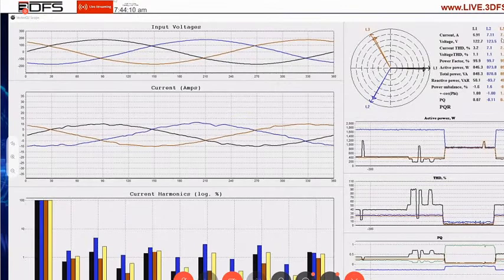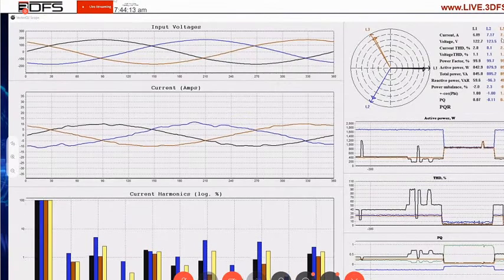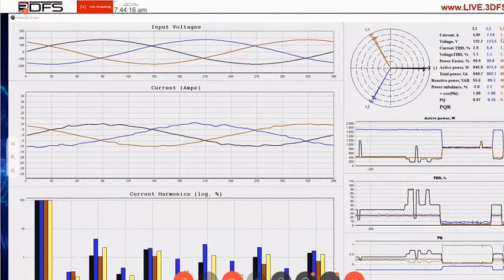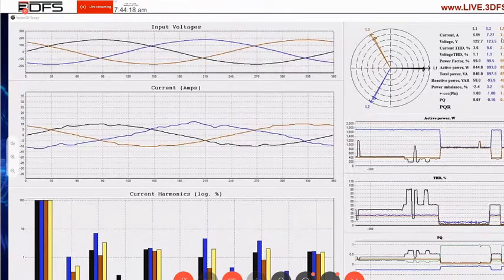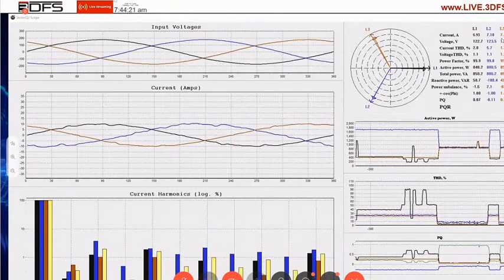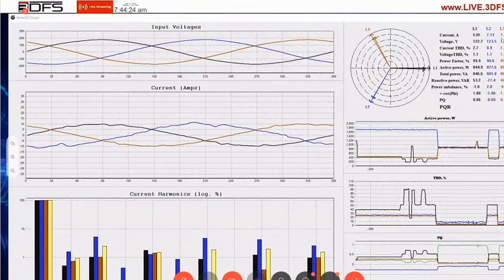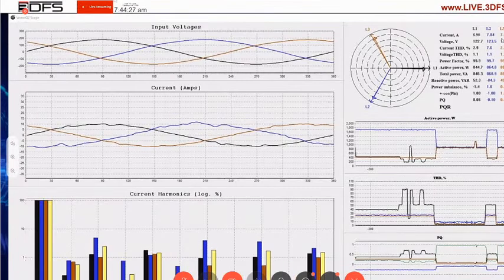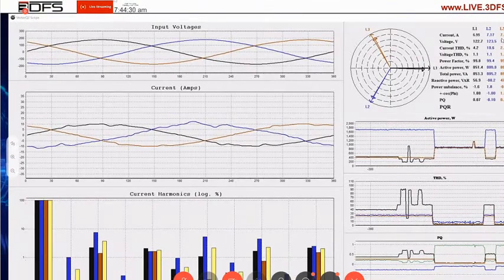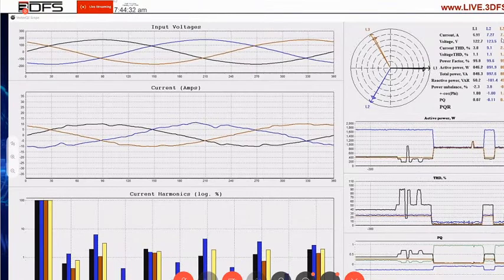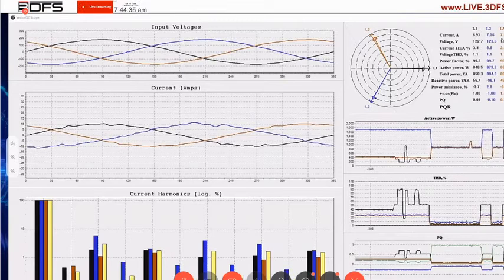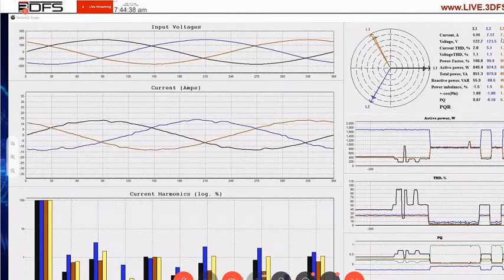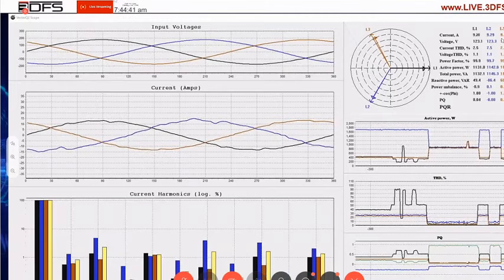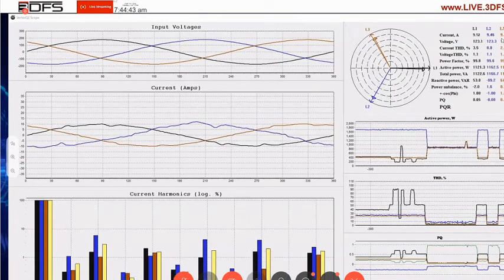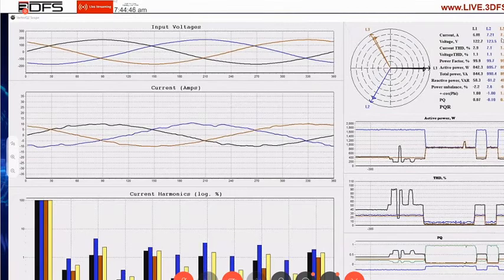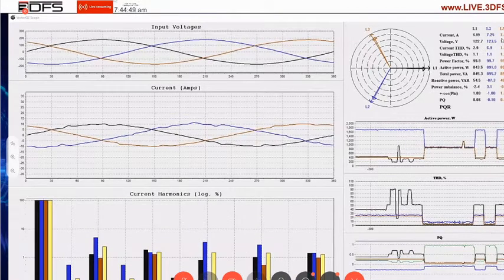Now the way we're doing that is within the device there's a DC bus bar. We are pulling the power equally from the upstream transformer. We know that in this moment there's 21 amps required, and the device knows there's 21 amps required in that moment. But it's 3, 14, and 3, or whatever the numbers were. So it pulls the 21 amps equally on all 3 phases and then redistributes it onto each phase so that it perfectly distributes the power and there is no neutral current.